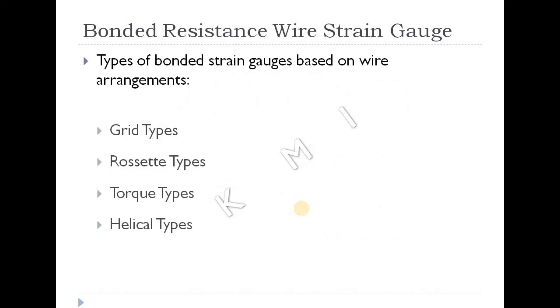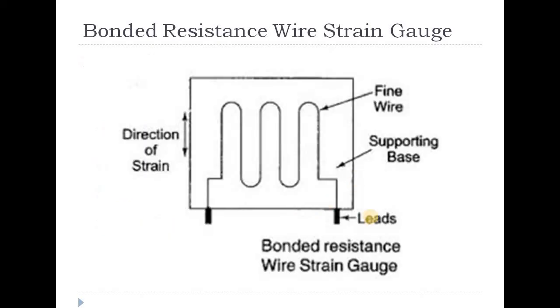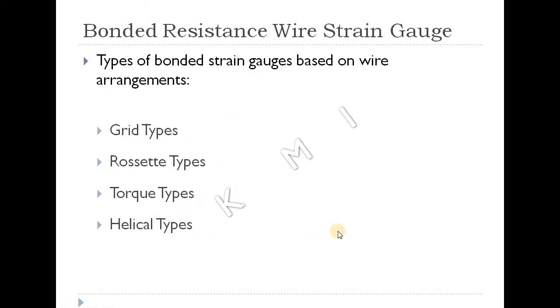There are four types of bonded strain gauge, based on the arrangement of the wire. The wire is uniformly distributed in different arrangements. The four types are: grid type, rosette type, torque type, and helical type.